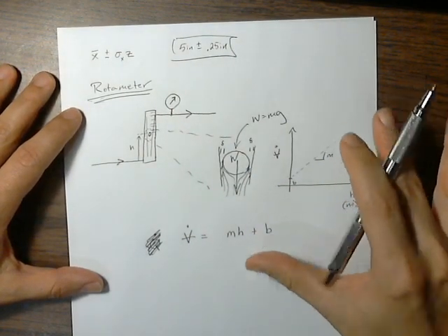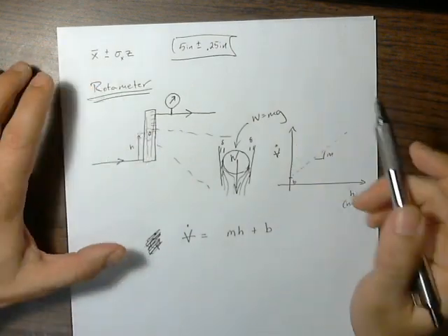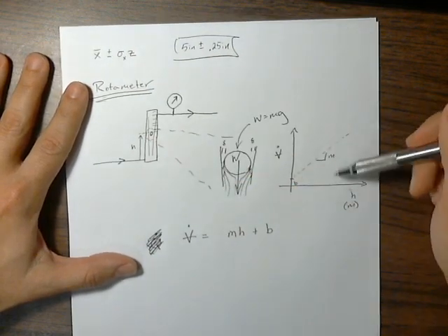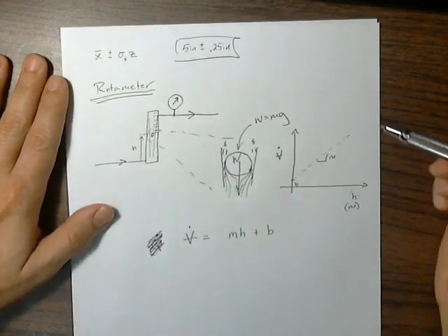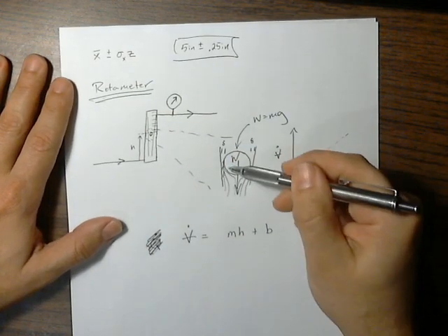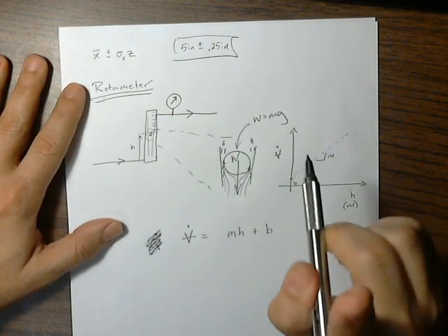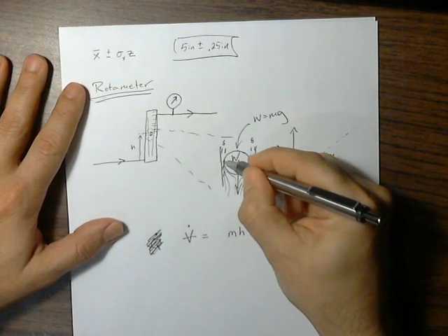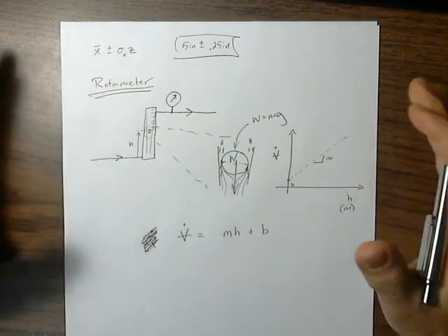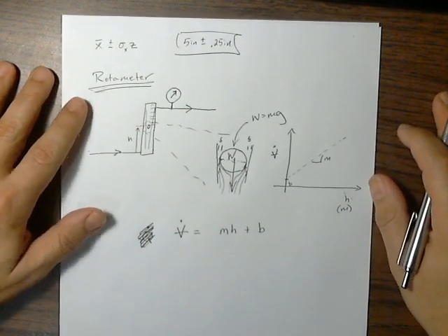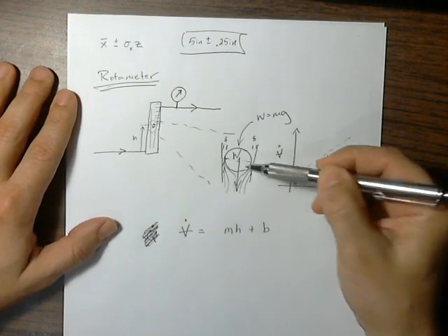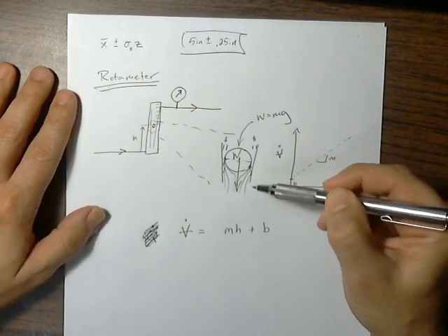The best rotameters, in my humble opinion, are rotameters that have a millimeter graduation and allow you to construct your own calibration for them. But where on the ball do you take the reading? There are an alarming number of manufacturers that tell you to read the scale from the middle of the ball. These manufacturers make me want to set the building on fire, because you have chosen the hardest place on the ball to reliably find visually.